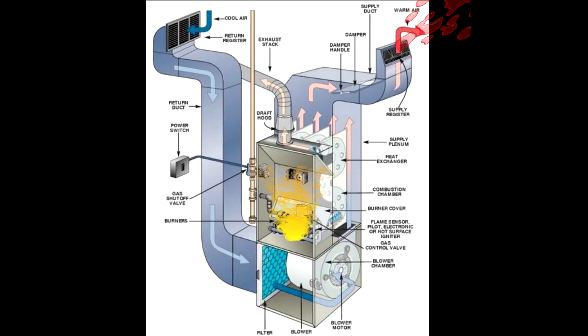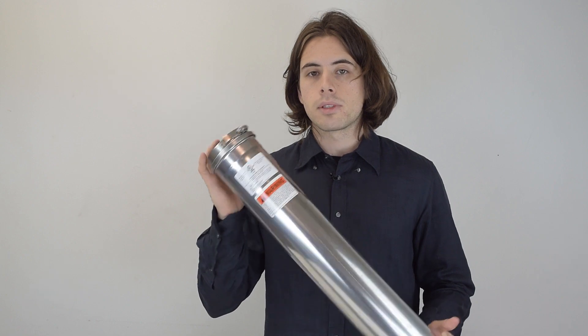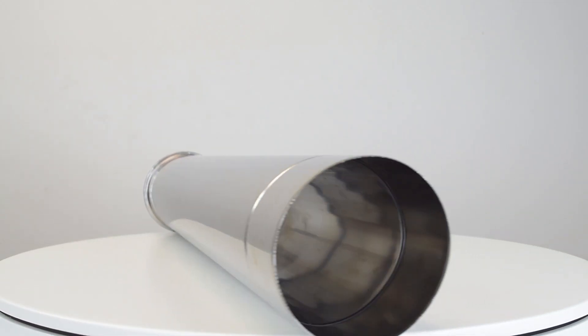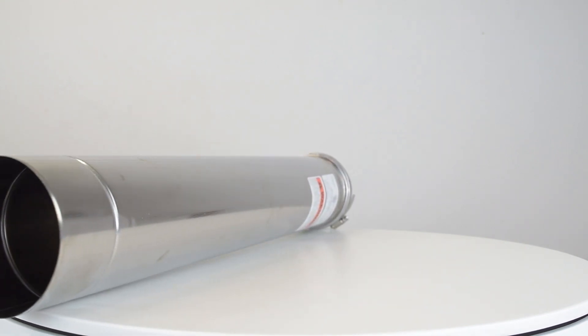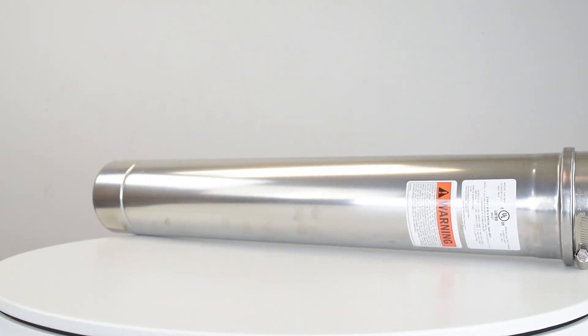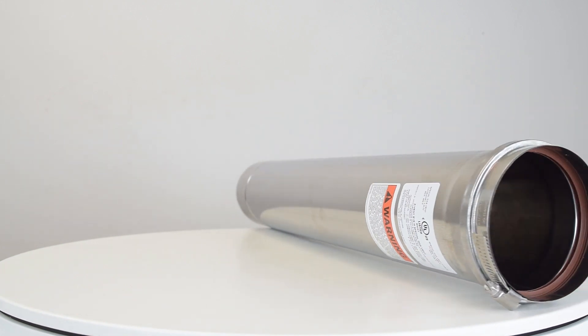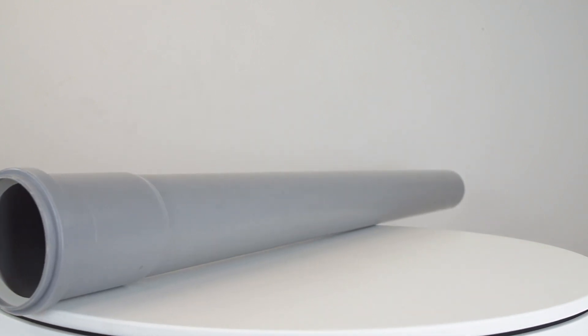Category three is any appliance that operates with positive static pressure in the vent and at a temperature that's high enough to avoid condensation in the vent. Due to the high temperature of category three appliances, you should use Z-Flex venting most of the time, but Centrotherm venting is usable if the temperature on your appliance is low enough — check specifications to make sure. Category three products are direct sidewall vented. Positive pressure requires joints and flue material to be sealed. Because these 80% appliance flue gases are close to the dew point and the vent material is single wall, corrosion resistant materials must be used. Drains are typically incorporated to remove flue condensation before it enters the heat exchanger. Category three has also been used to solve installation problems where no appropriate flue is available.